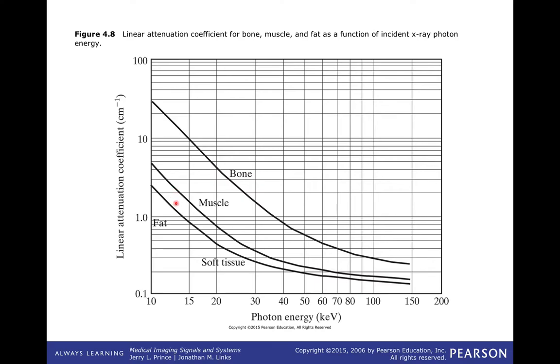You basically have to work at higher energies to get a signal out of the back of the patient. In the past decade, CT used to always be done around 120 kVp because that's how X-ray tubes were built. But now there's a whole new generation of tubes that can give you 80 kVp peak beams at really high mA — like 1400 mA at 80 kVp — so you still get signal out the back of the patient while operating at lower energy, which gives much lower dose to the patient.